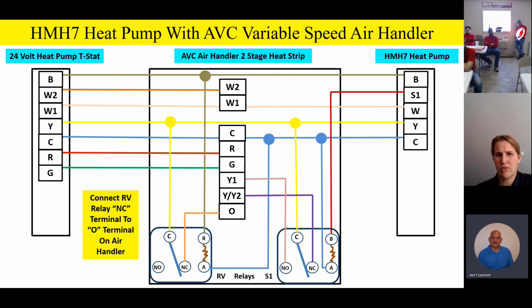That RV relay is strictly for the indoor variable speed product to give it 24 volts on its own O signal inside in the cooling mode for advanced functions. This has nothing to do with the outdoor unit. So just like we had before, the thermostat has to be configured for B for heating. It's just that what we're looking at right now is the O terminal strictly on the indoor unit, which has to have an O signal in the cooling mode for some advanced functions. And that's the only reason that RV relay is there: to provide 24 volts to the O signal on the indoor unit only, variable speed, for advanced blower functions inside. That was a good question.